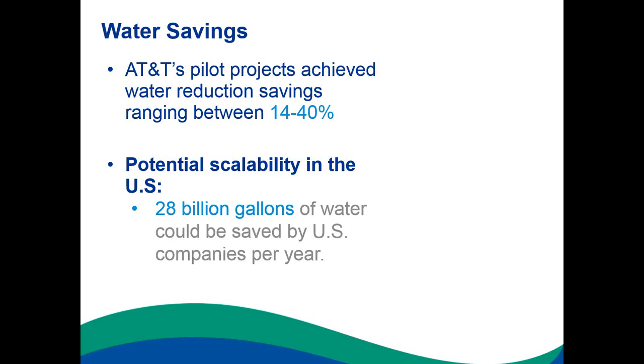But at the end of the day, they were looking for scalability, and the different options identified offered the potential to greatly reduce water use across their portfolio. We estimated that if the measures used—either technical or free air cooling—were adopted by commercial and institutional building operators across the U.S., just achieving 14% savings could save about 28 billion gallons of water per year across the U.S.